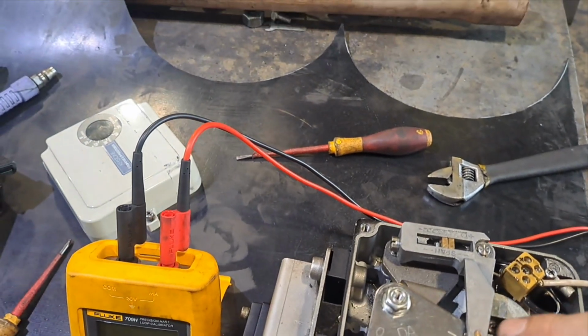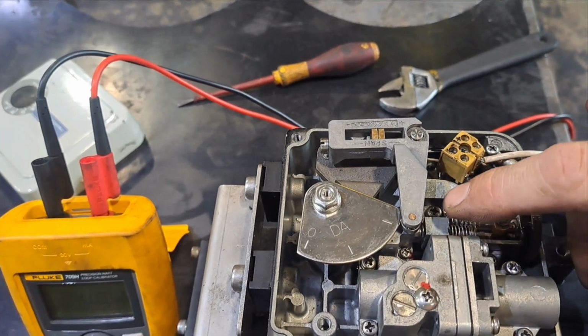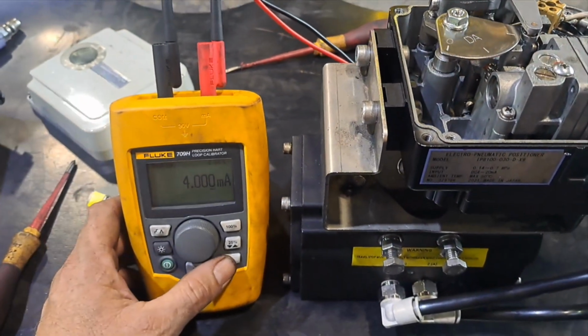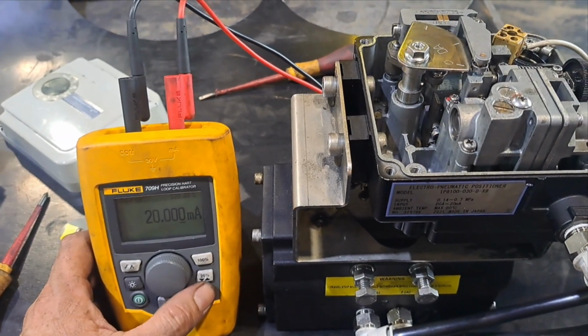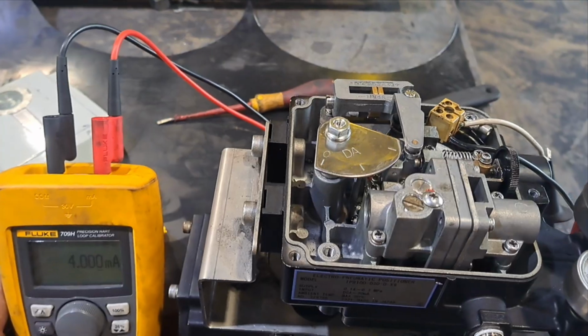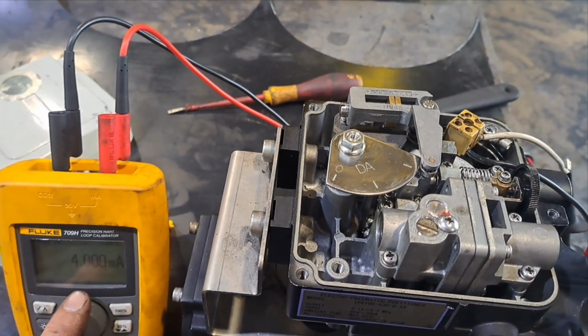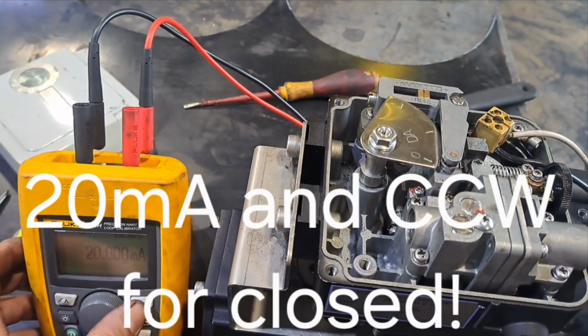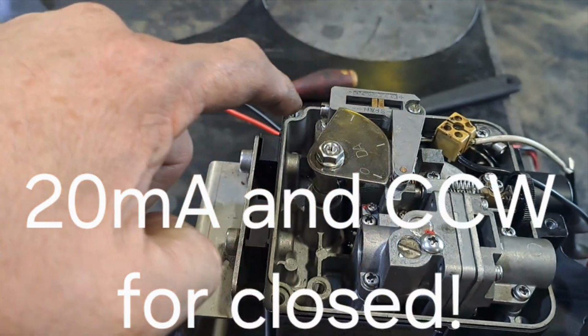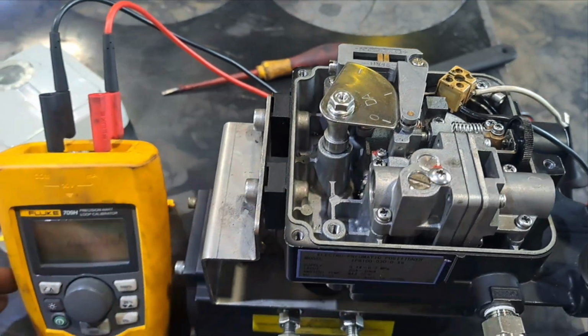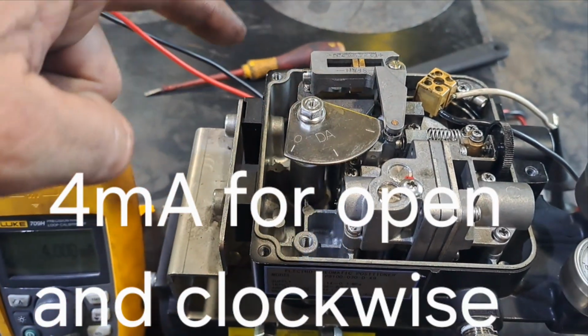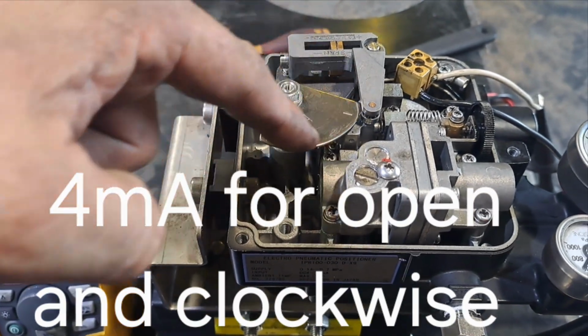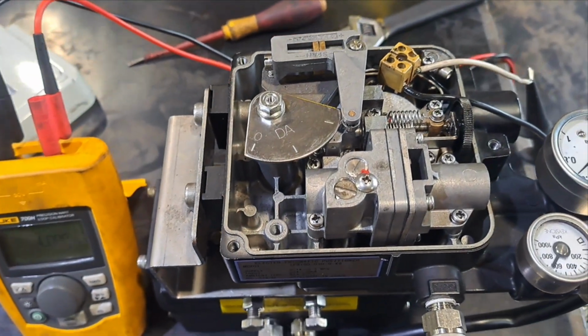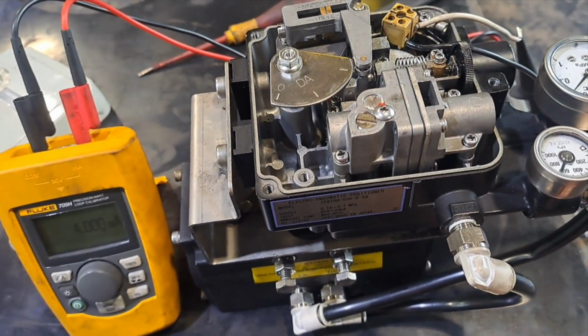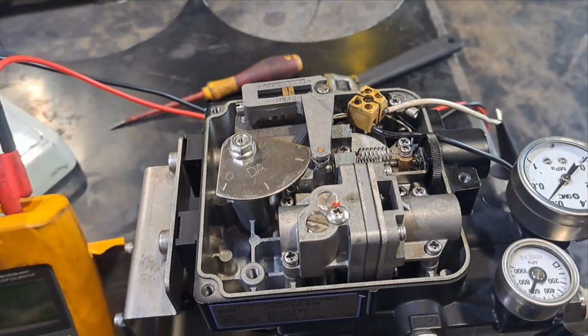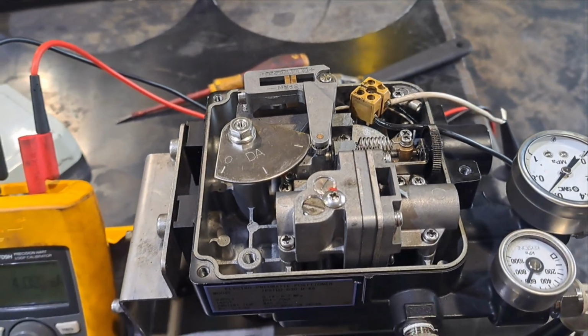For the last two setups, this one included, when we are trying to do a fail open, we have to put the 4 milliamps towards open. And to get that done, we have to get the output from the PLC swapped over. Normally, your output from the PLC, if you have 0% output, will be the 4 milliamps, and the 100% output will be the 20 milliamps. But for these, you have to get them swapped over, so that your output signal for 0% is 20 milliamps, and your output for 100% is 4 milliamps. The complete opposite to what we would normally do.